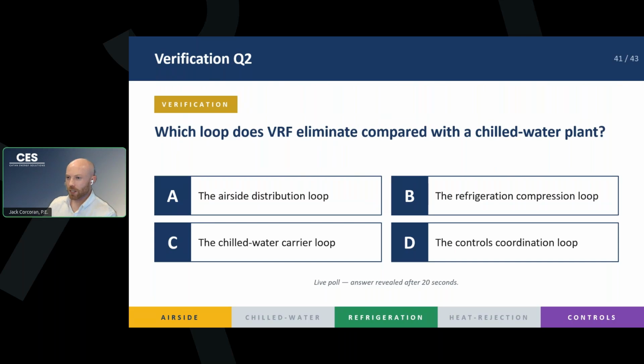Question 2, which loop does VRF eliminate compared to a chilled water plant? We think back to our 5 loops, they're on the bottom of the screen. Maybe that's a hint, but A, air side loop, B, refrigeration loop, C, chilled water loop, D, controls loop. I'll give you a second to figure out the answer. And if the bottom didn't give it away, it's C, chilled water loop, right? We only use our air side, refrigeration, and controls loop in a VRF system.